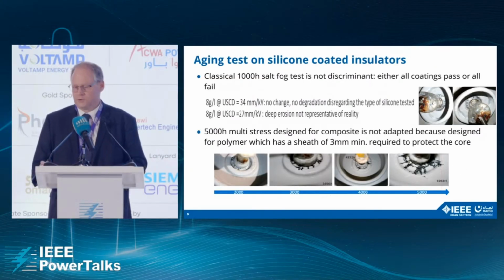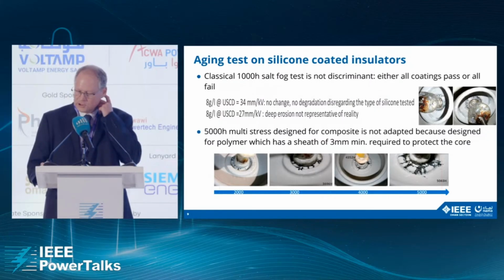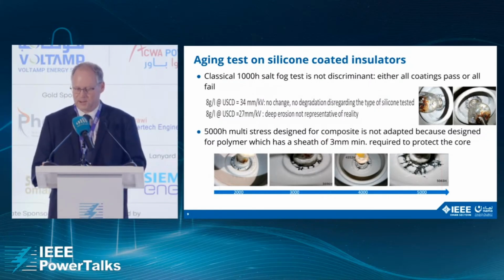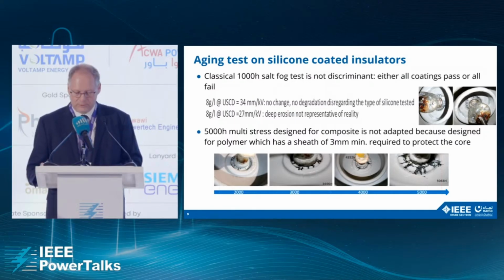It is today understood that the aging process of silicone material comes with several changes in the properties of the material. Loss of hydrophobicity will progressively let the leakage currents increase and subsequently start an erosion process. This has led to numerous attempts to define an erosion test. The various options available for evaluating the aging of silicone coatings on glass or porcelain insulators were the following.